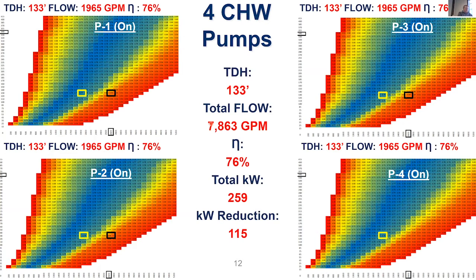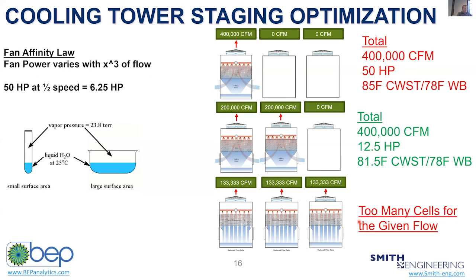Okay, so we're going to go on to tower staging. I'm trying to give examples of things that are really simple here that can have a huge impact. On tower staging, let's say I have 3 cooling tower cells in this example, and I'm running 1 cell. So what does a tower do? It wants to evaporate water to reject heat. The majority of its heat transfer is due to evaporation, so it needs to evaporate water. And evaporation is a function of heat transfer. That's why it's equipped with a film fill to spread out that water.